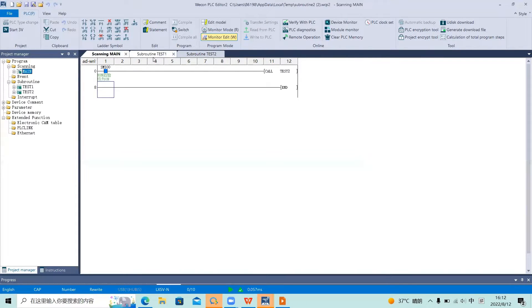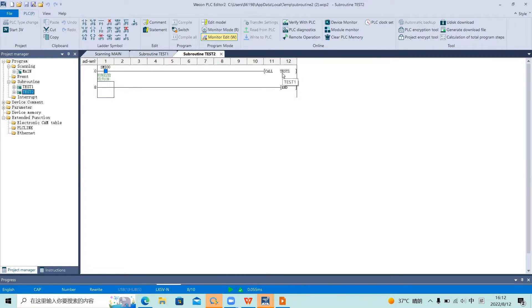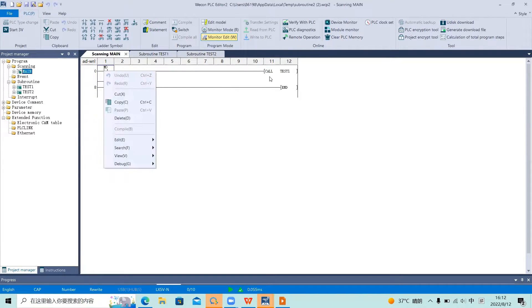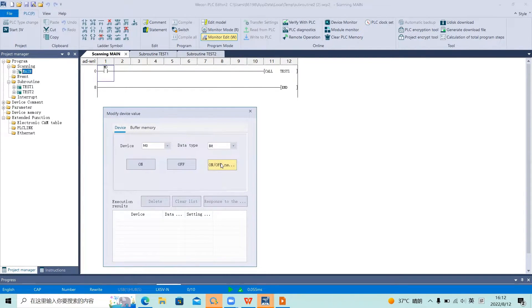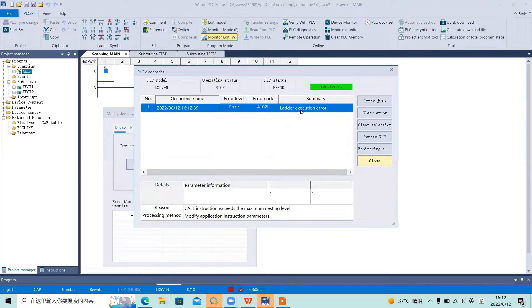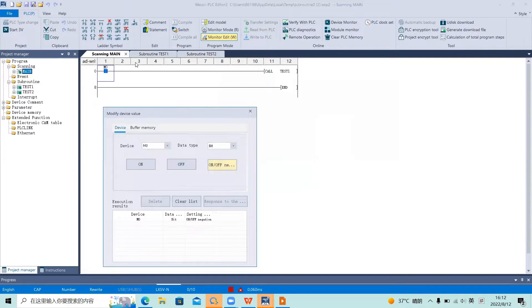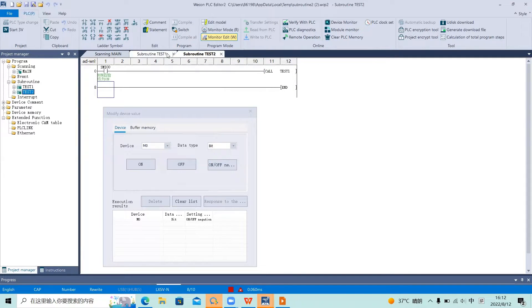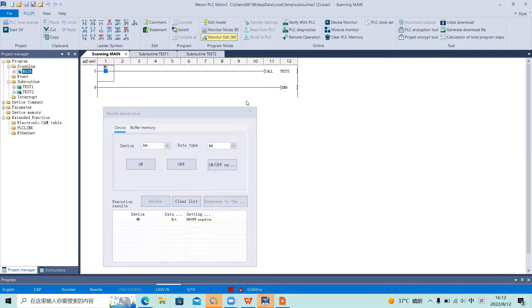In this project, I have built two subroutines: test1 and test2. In subroutine test1, I call test2, and in subroutine test2, I call test1. In this situation, when we call subroutine test1, the PLC will have an error. It shows a ladder execution error, because in subroutine test1 we call test2, and in test2 we call test1 — it will have no end, so the PLC will report an error. We can't use subroutines in this mutual-calling way.